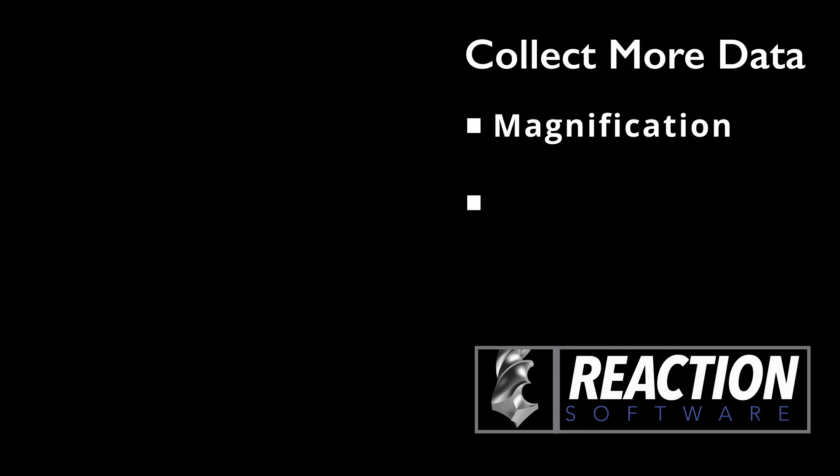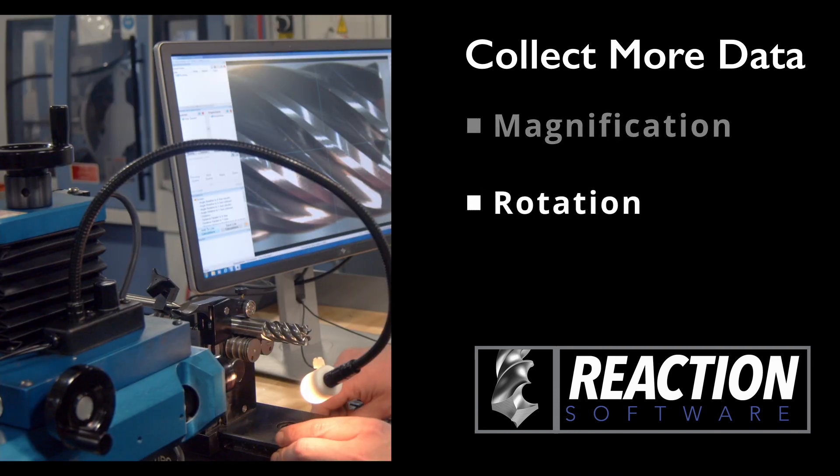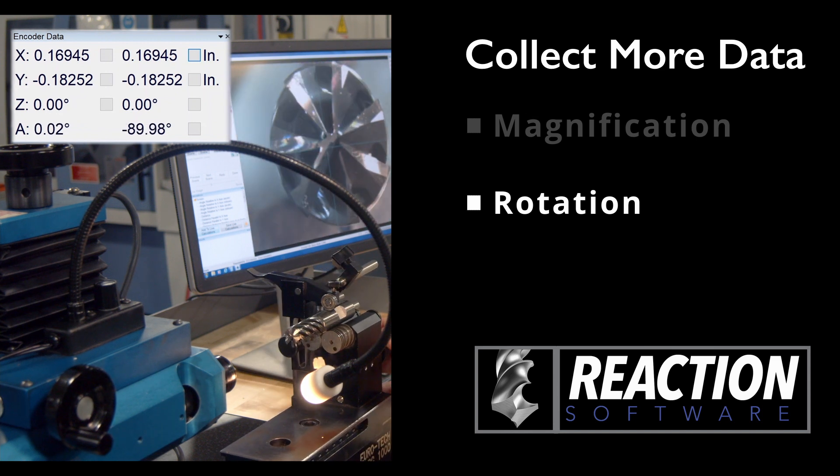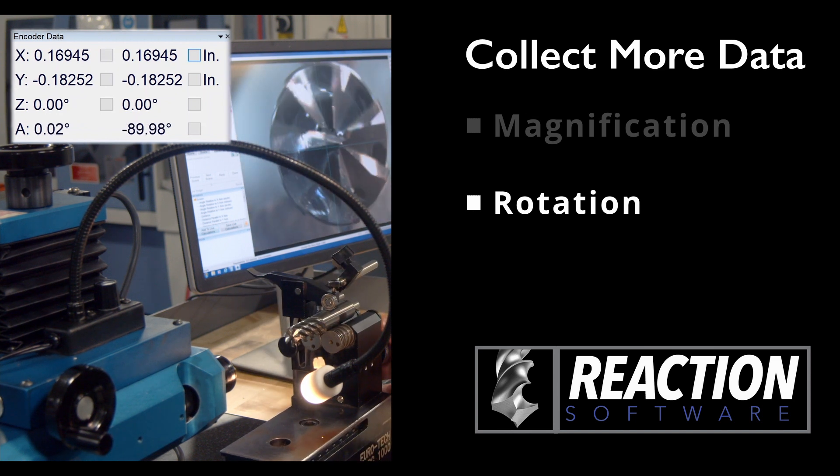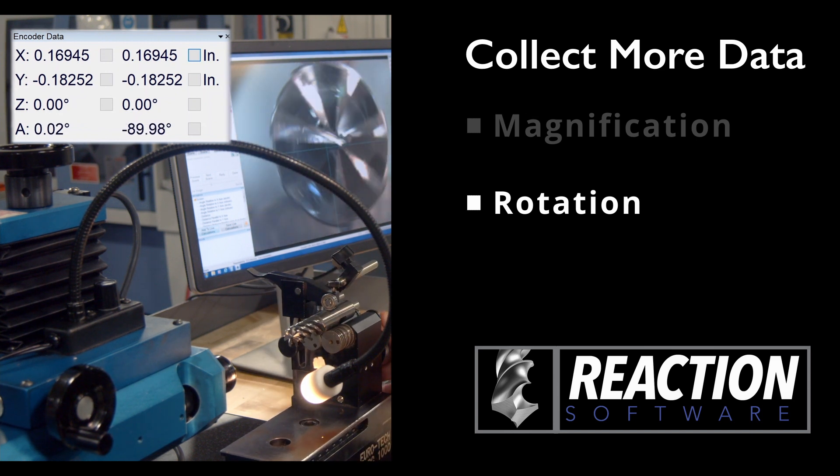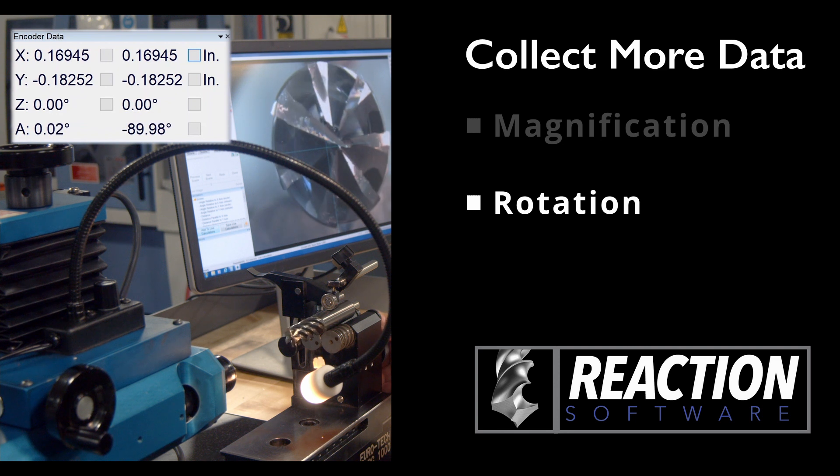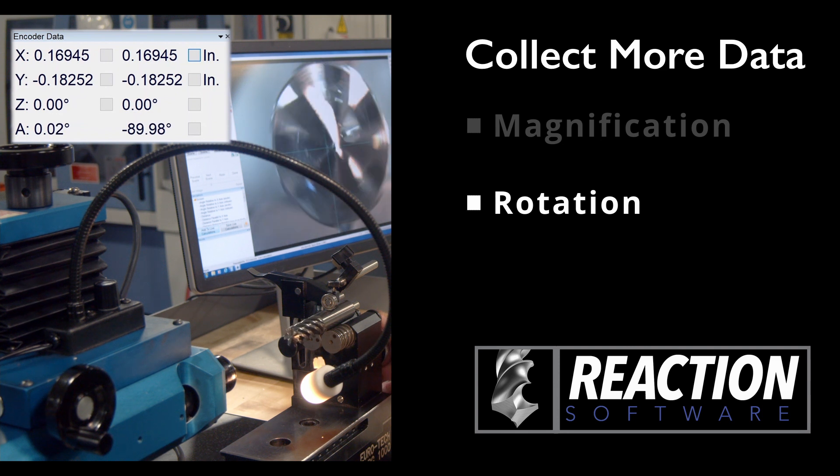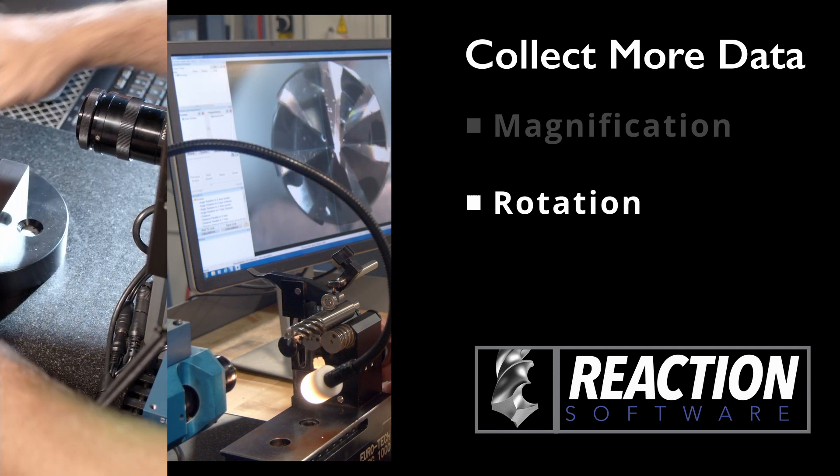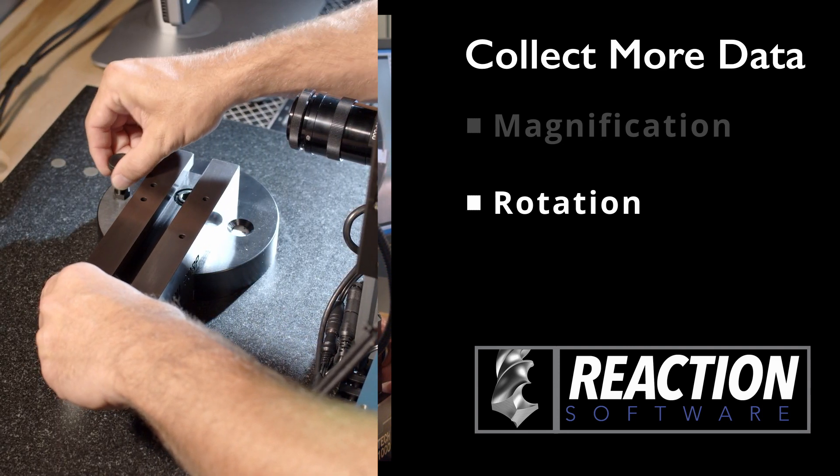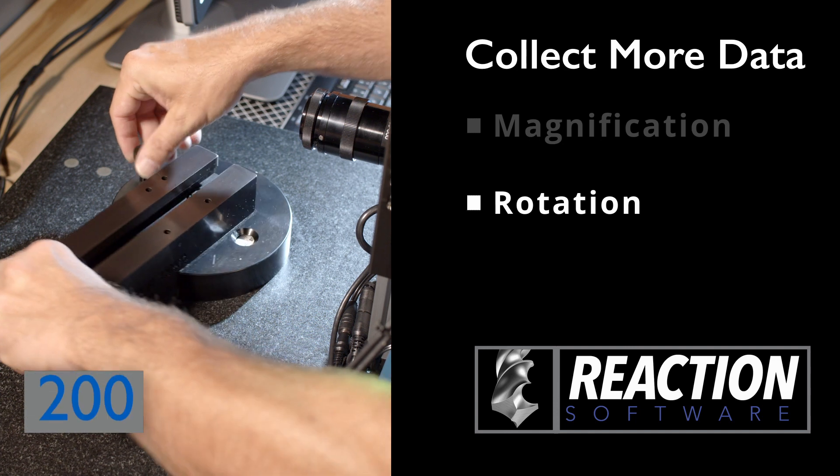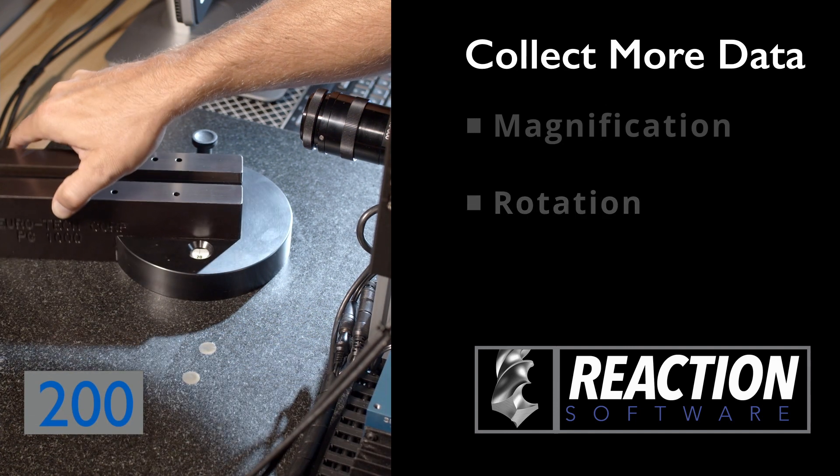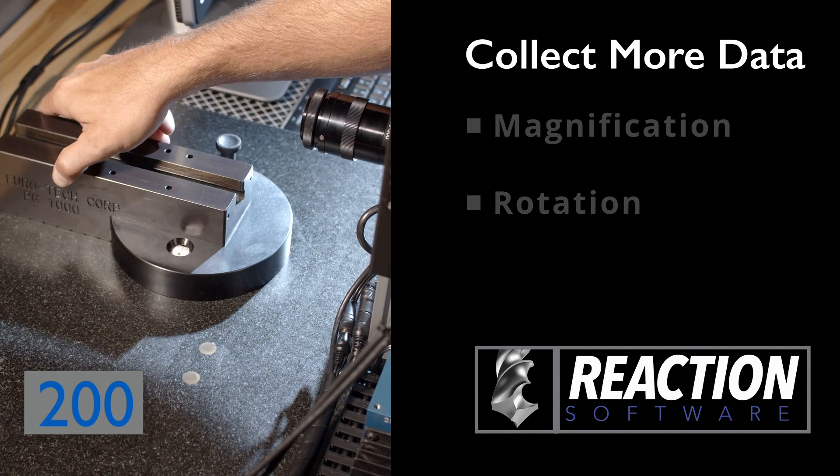The 400 sends data on the rotation angle of a tool to the software as well, which makes it much easier and more precise to set up multiple inspections with identical parameters. The 200 utilizes a plunger and three preset angles for tool inspections.